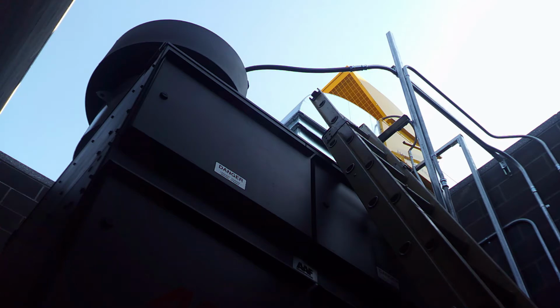If it's working right, you can see the conduit goes up there to a solenoid. When this thing is engaged, you'll hear the solenoid buzz, and that opens, and the damper comes down. Now putting it back, particularly like this, is what I see people doing.